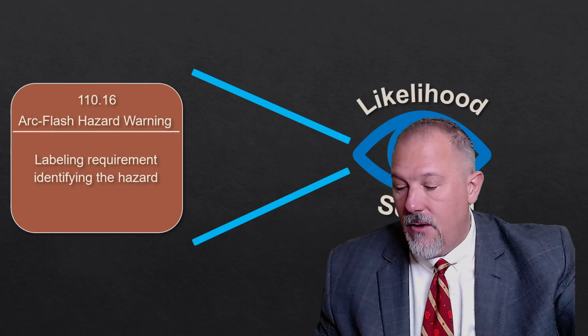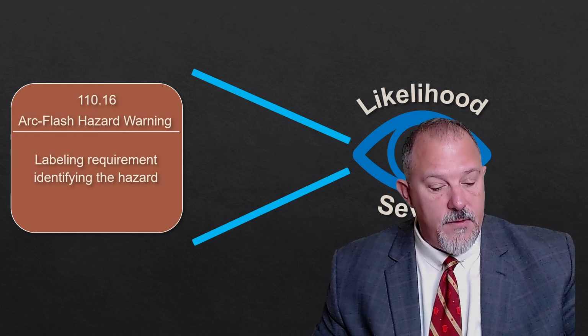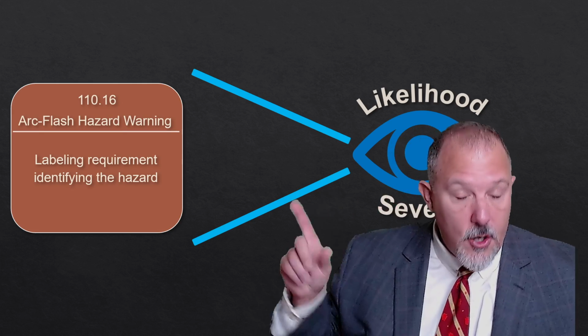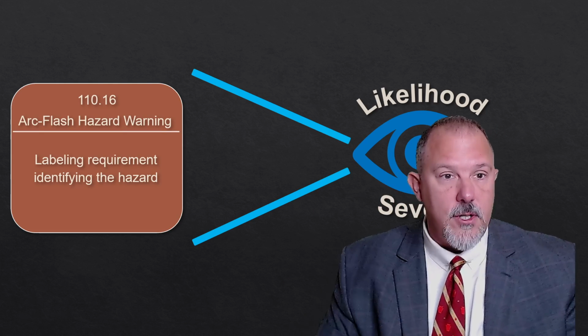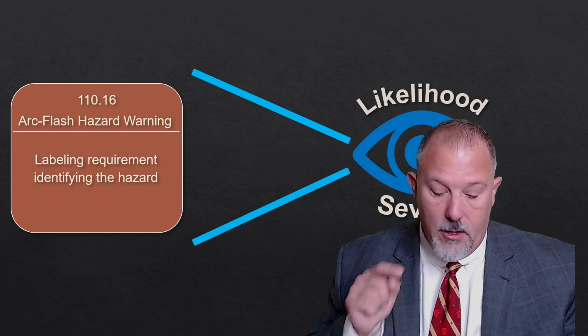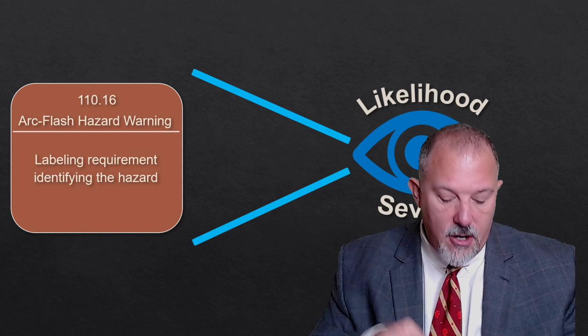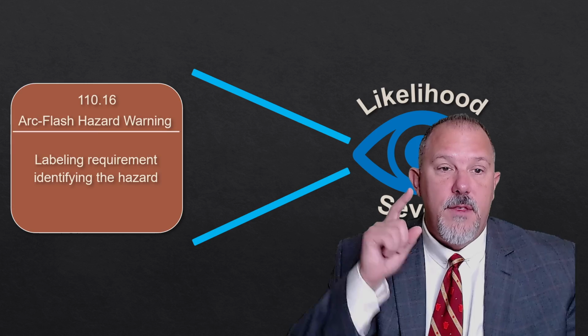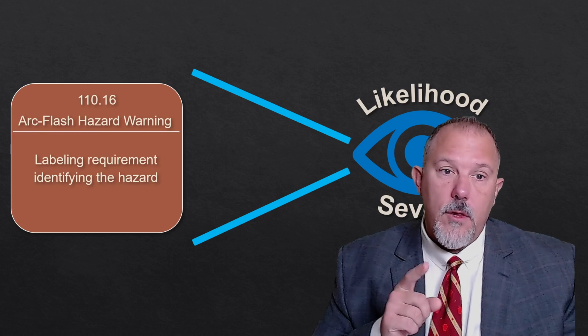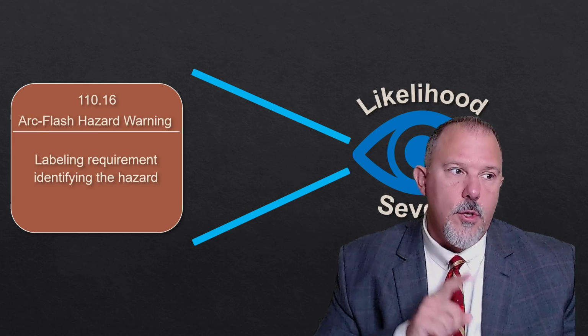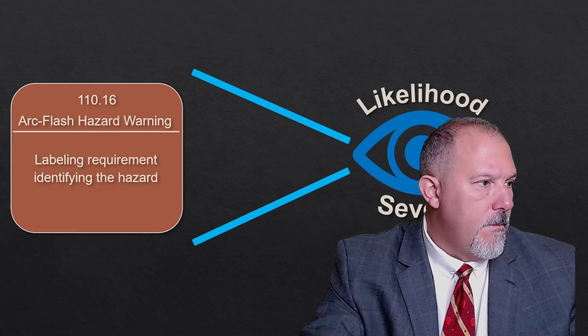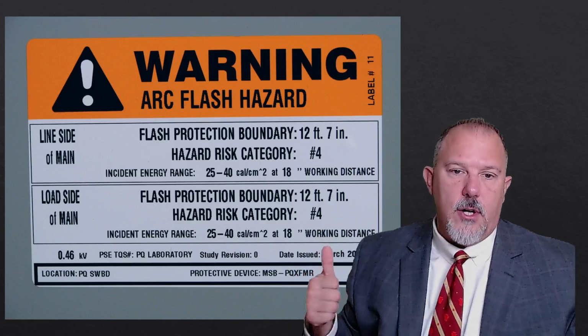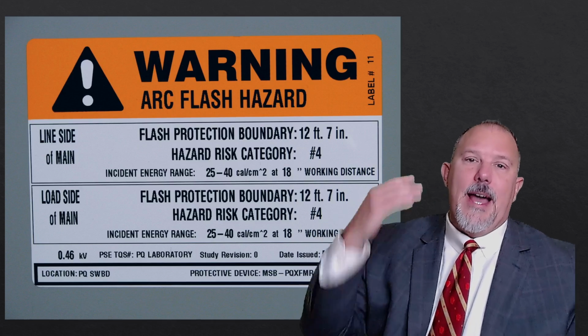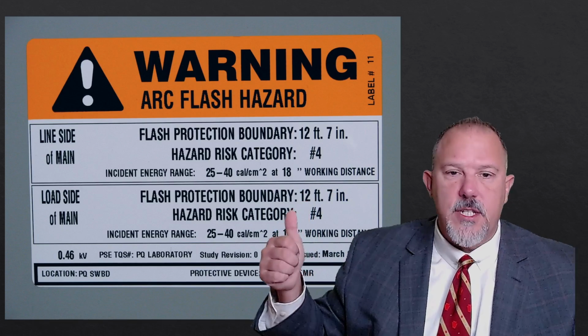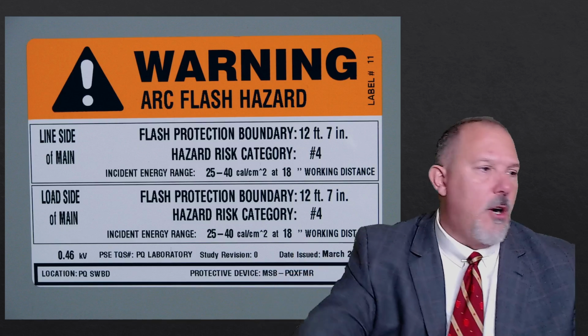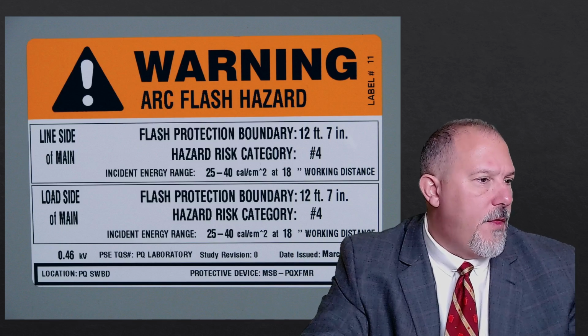110.16. Now I'm working out of the 2020 version of the National Electrical Code. I do have earlier versions of the National Electrical Code, but I am going to be primarily looking at 110.16 as an arc flash hazard warning. Now, this section, when it first went into the code, was looking for a label like this on all equipment. It wanted an actual arc flash, calories per centimeter squared, working distance, all this other good stuff.